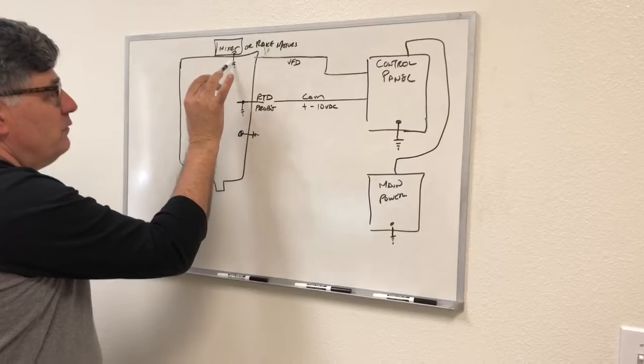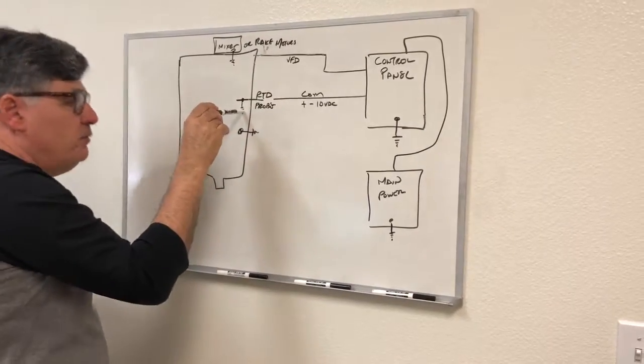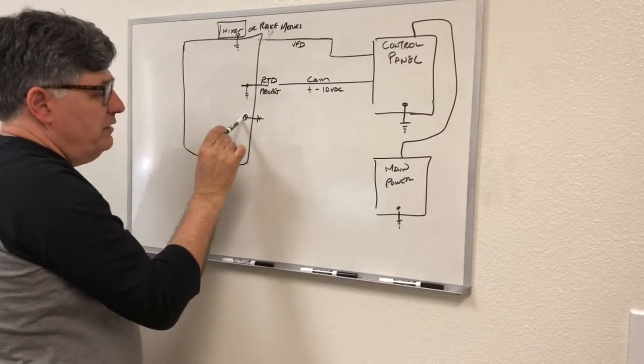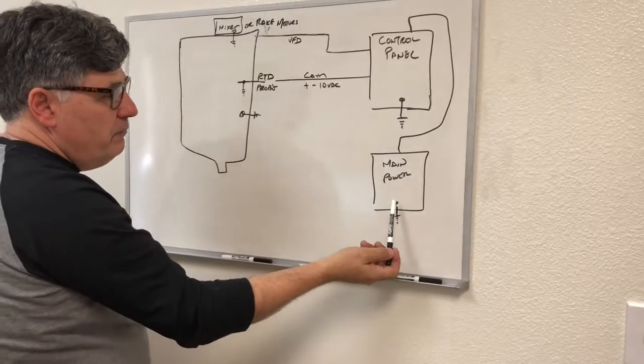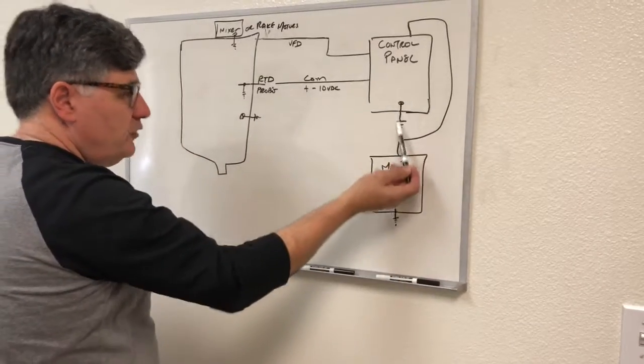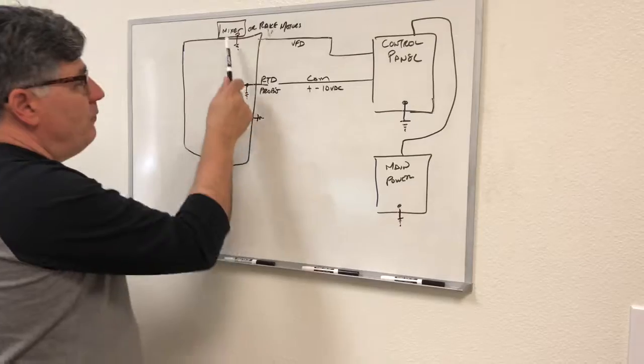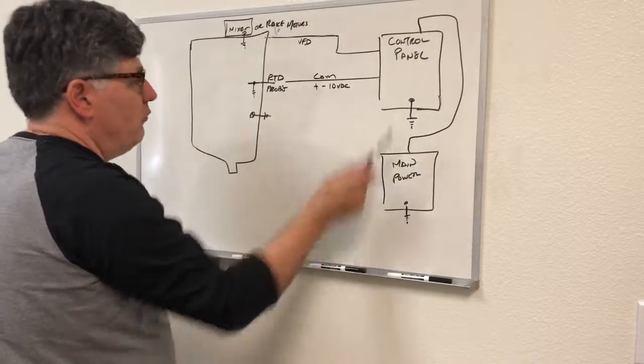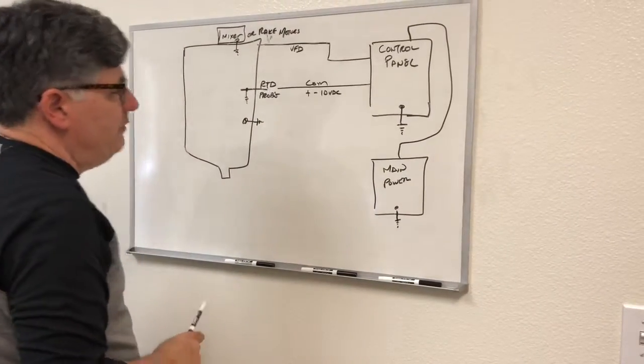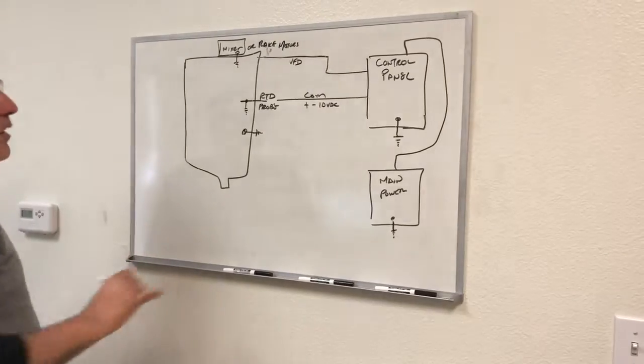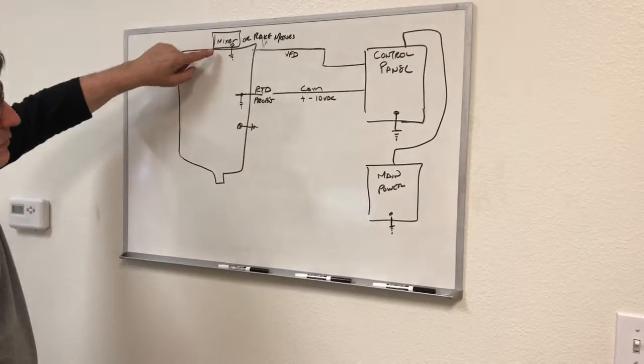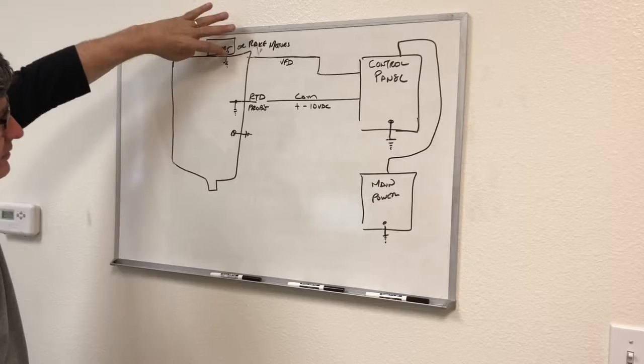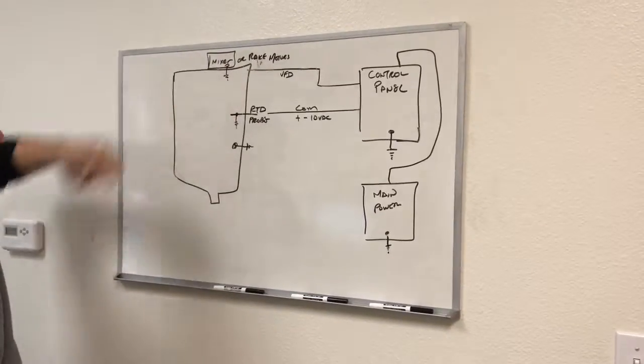And notice that the mixer motor is grounded, the RTD probe is grounded, and the tank is grounded, to the main power panel, which is grounded, and the control panel, which is grounded, forming one complete grounding situation back to the main power. This is where the problem is. The problem is the fact that the mixer and rake motors are actually attached to the vessel.